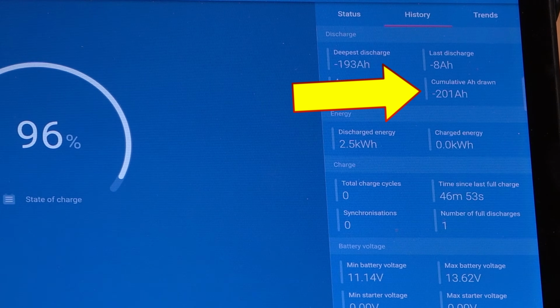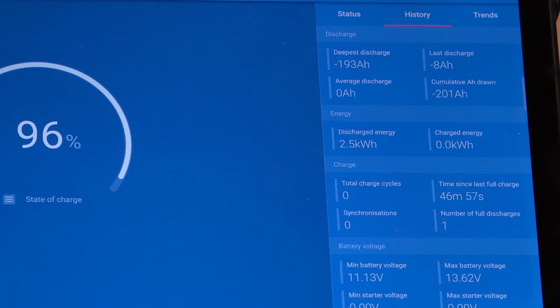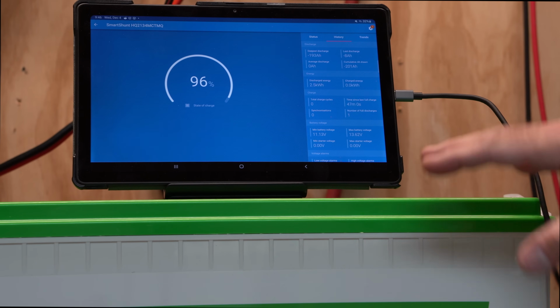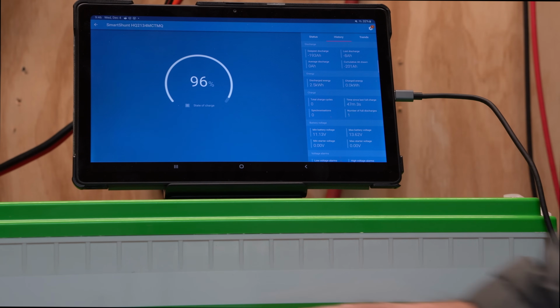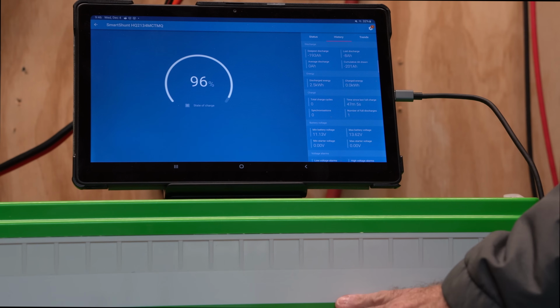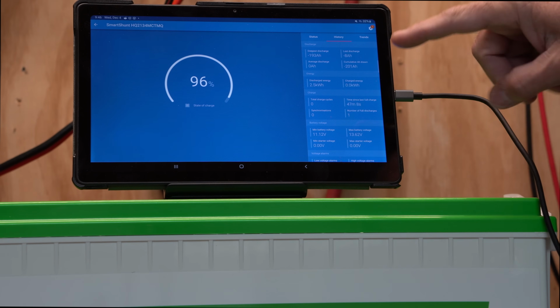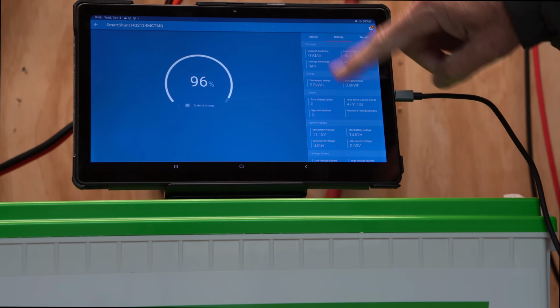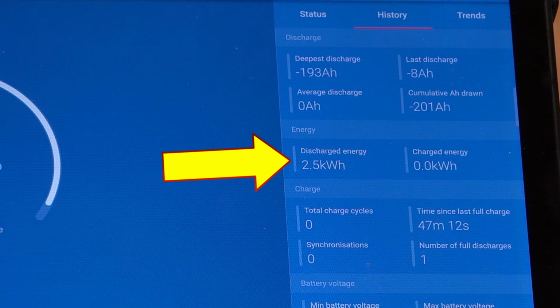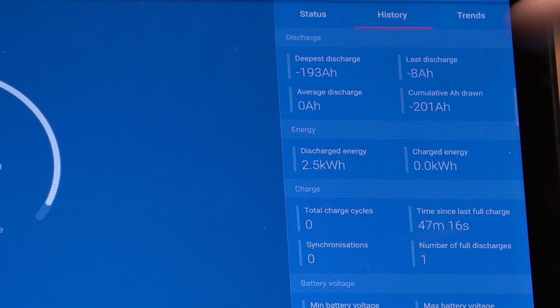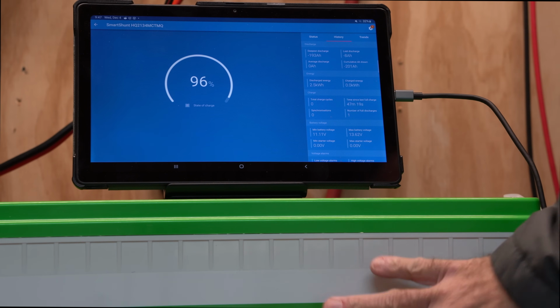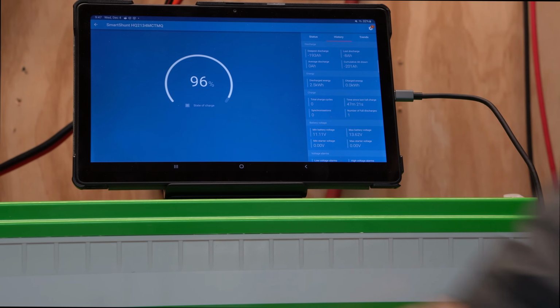We are already at 201 amp hours, so we're already getting more capacity than is rated from this battery at 200 amp hours. And the watt hours, if you do the math on this, should be about 2,560 watt hours. Now, I don't have the precision on the discharged energy, but we are at 2,500 and something, it doesn't go past that first decimal place. So we have been getting the rated capacity of this battery.